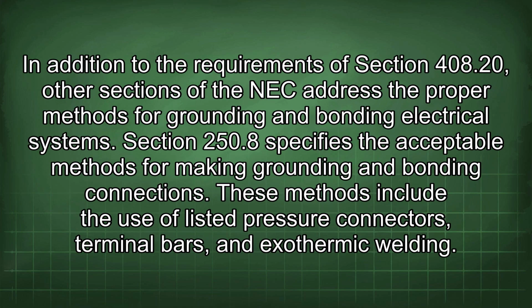In addition to the requirements of Section 408.20, other sections of the NEC address the proper methods for grounding and bonding electrical systems. Section 250.8 specifies the acceptable methods for making grounding and bonding connections. These methods include the use of listed pressure connectors, terminal bars, and exothermic welding.